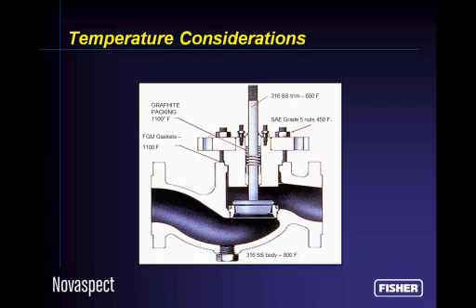In addition, some valves open and close frequently and they heat up and cool down quickly, and therefore we get thermal gradients in the valve over time. And some parts, depending on their materials, have different thermal coefficients of expansion than other parts that might be in the valve. And therefore, as the valve heats up and cools down, we have to pay attention to the rate at which each part shrinks and expands so that we don't end up with parts that stick together and make it a poor control valve.